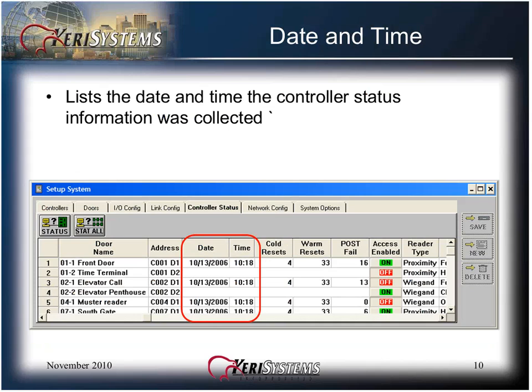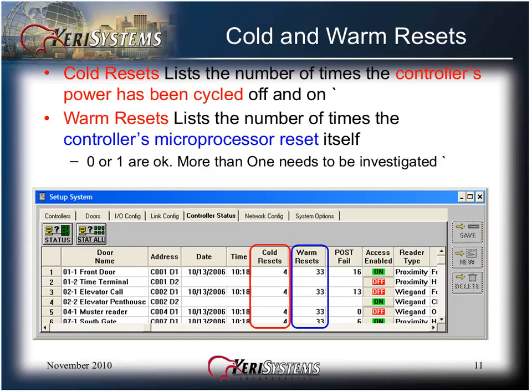The date and time columns list the date and time the controller status information was collected. This is the time and date of the controller's internal clock and calendar, and it should be accurate to the current local time and date. The cold and warm resets column lists the number of times the controller's power has been cycled off and on. The number of cold resets can grow quite large in an older system that has had a lot of service. The warm resets list the number of times the controller's microprocessor reset itself. Zero or one are okay; more than one needs to be investigated in the warm reset column. All of these numbers will reset to zero if the controller's RAM is reset.